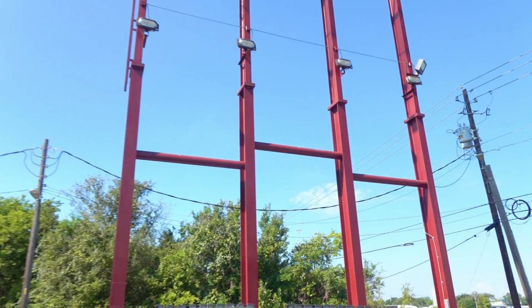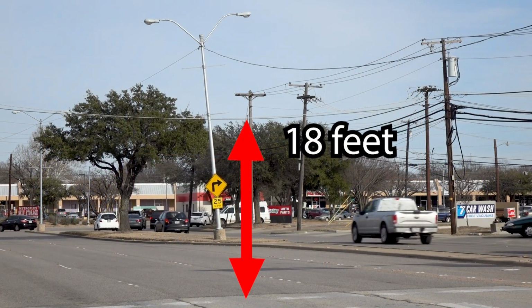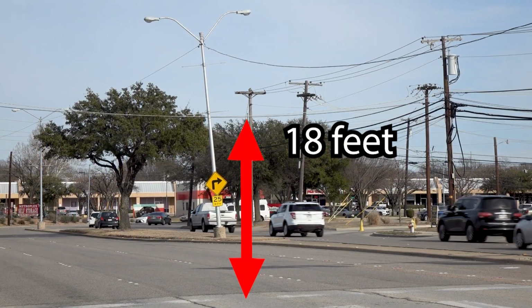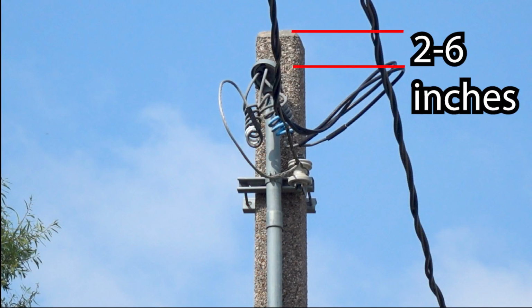Where they cross over commercial property, a right-of-way that is subject to agricultural equipment, such as mowers or truck traffic, the clearance must be at least 18 feet. The weatherhead is to be placed between 2 to 6 inches from the top of the support structure. A visual estimate of this distance can be made by the inspector from the ground.